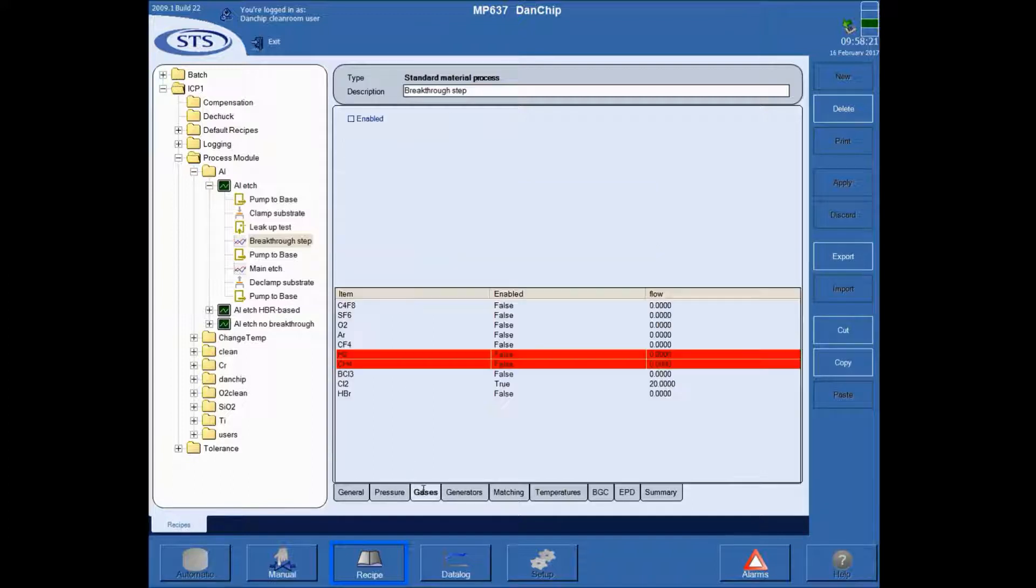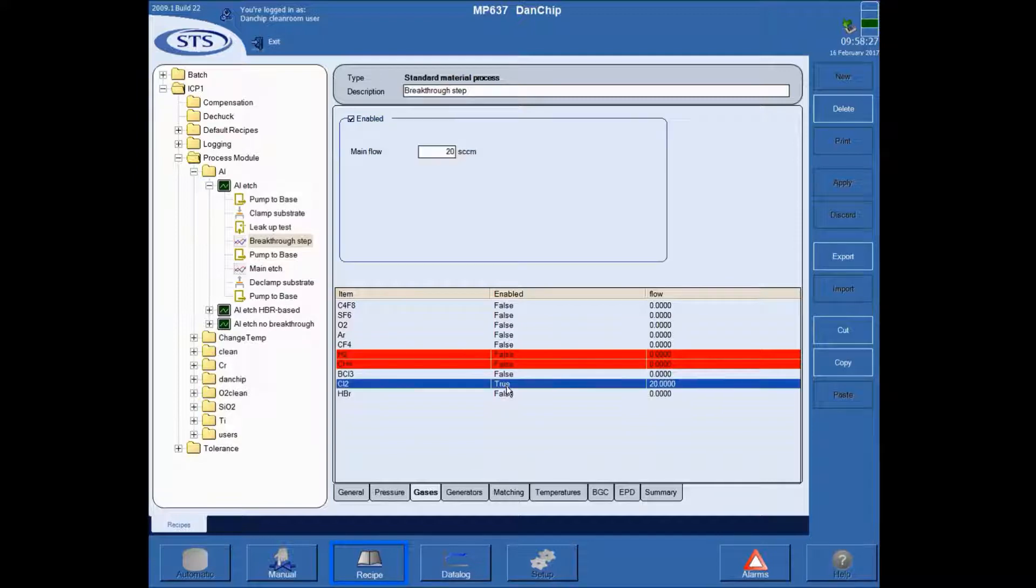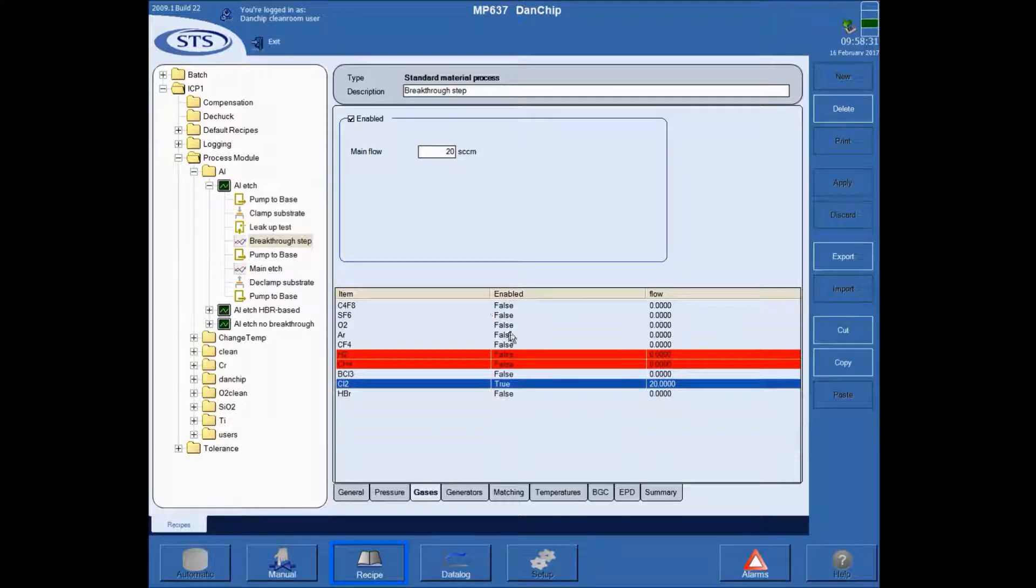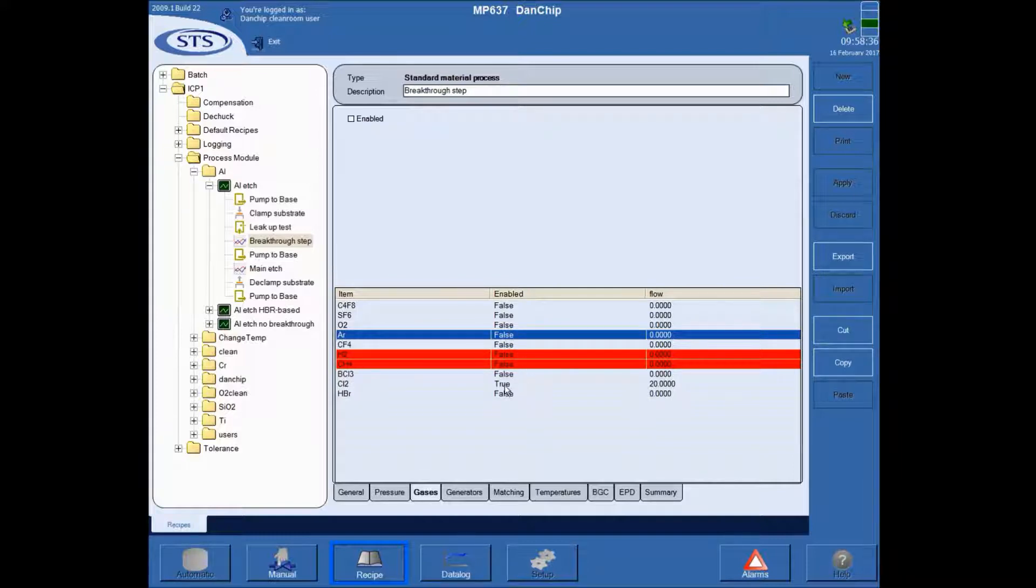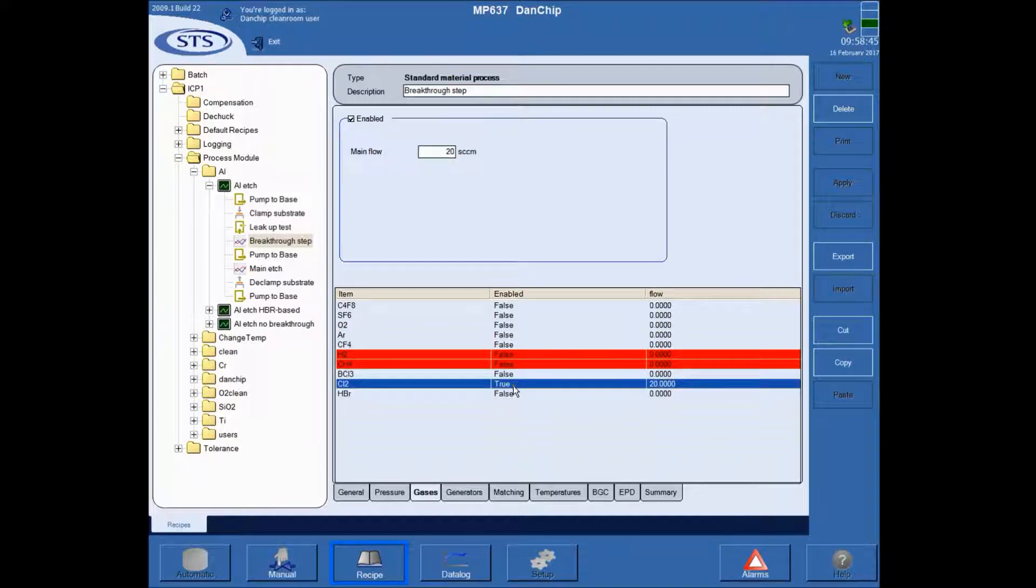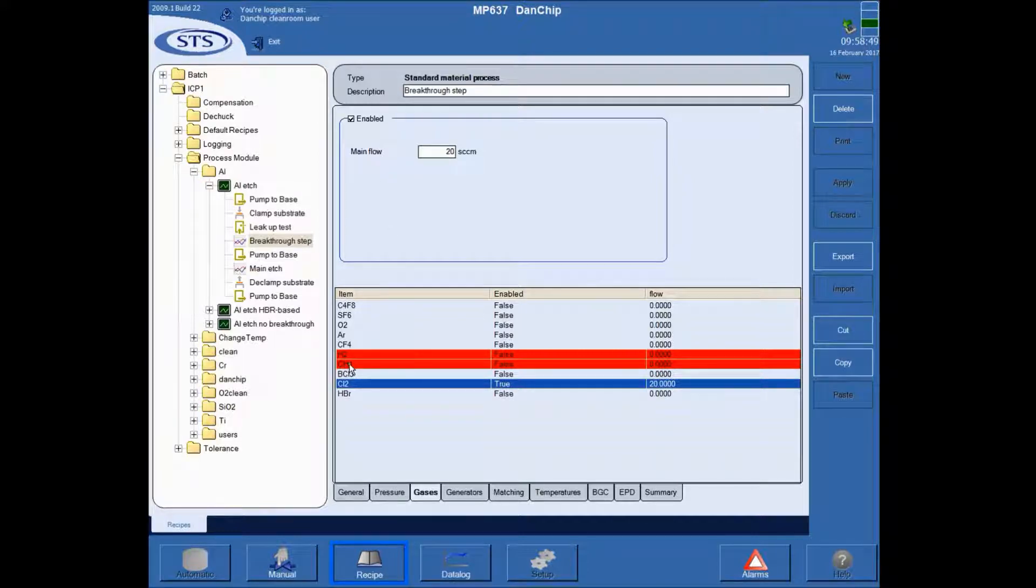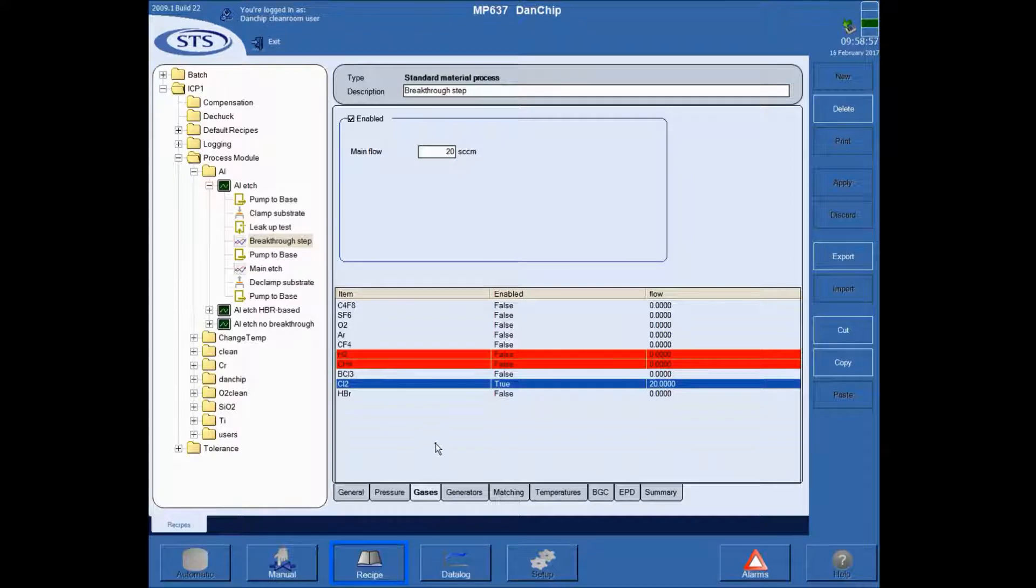Under gases, you have the collection of gases down here. In this case, you can see that the only one that is enabled is the chlorine with a certain flow. The other ones are not enabled, so it says false. You can also see that some are red, and that is because there is an interlock. When you have chlorine enabled, you won't be able to run hydrogen or methane. That ensures that you cannot make a gas combination that is explosive or something like that.